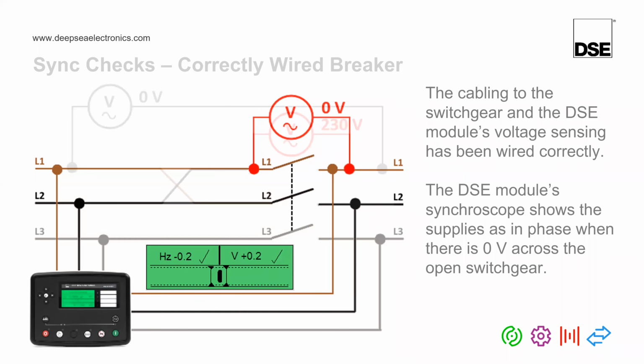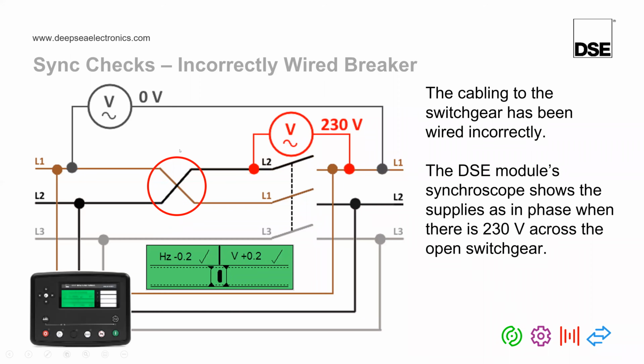However, if the following mistake was made, where for some reason the wires were swapped between the DeepSea module sensing and the breaker, then unfortunately the DeepSea module would not detect this problem until it is too late. As you can see on the left-hand side, the DeepSea module is measuring L1, L2, L3. On the right-hand side, it's measuring L1, L2, L3, and it's measuring 0 volts between them. But because somebody has crossed the generator phase wires to the breaker, actually we have 230 volts across this breaker, which the DeepSea module does not detect because the fault has happened after the generator sensing.